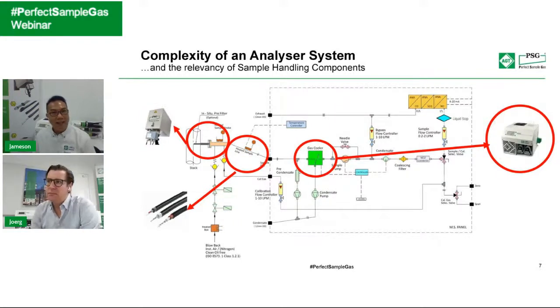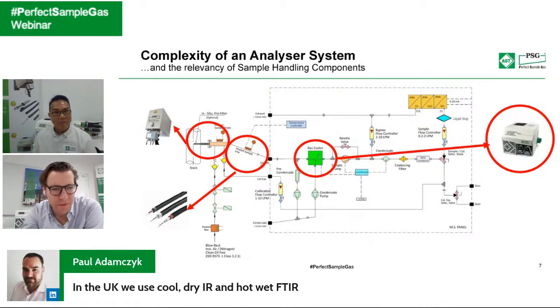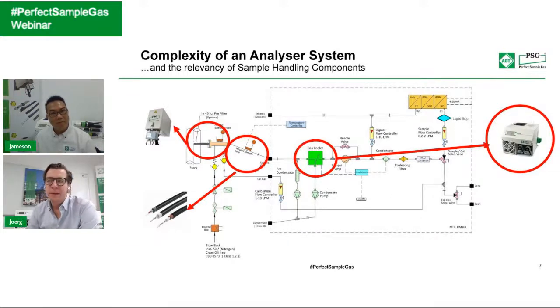But I mean the IR or the cold extractive. By the way, Paul from the UK just confirmed that's cold dry IR and hot wet FTIR, exactly what we said. It depends on how many components you have to measure, and I would say if it's these 3 standard components, CO, NO, SO, you wouldn't choose an FTIR because it's just oversized. So that really depends on what kind of measurement you're talking about here.